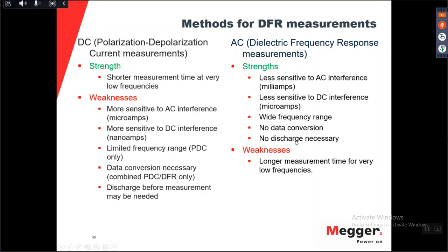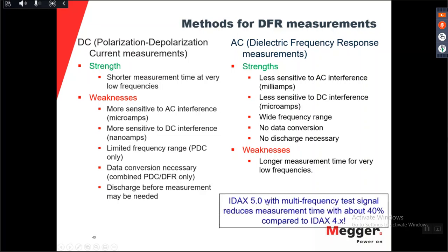At Megger, we have done a software that has a multi-frequency test signal, which means we inject 3 frequencies at the same time, and this reduces the measurement time to the same measurement time as a DC current measurement, but it has the accuracy of an AC method.